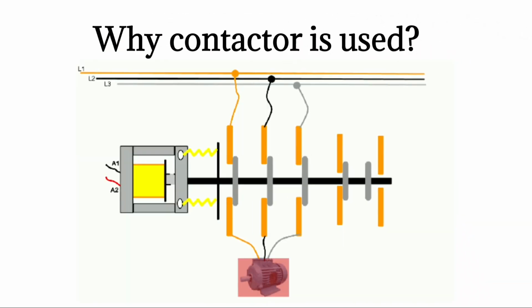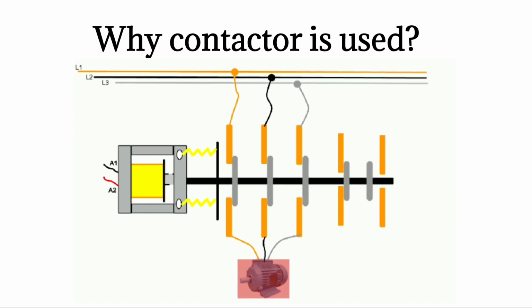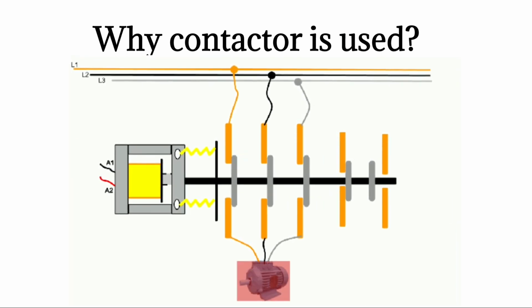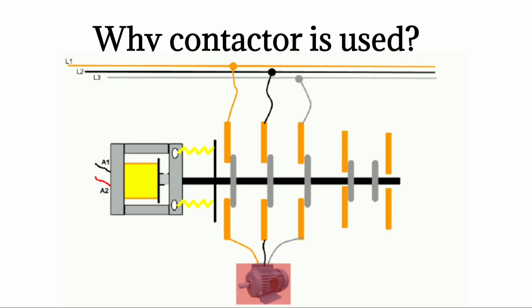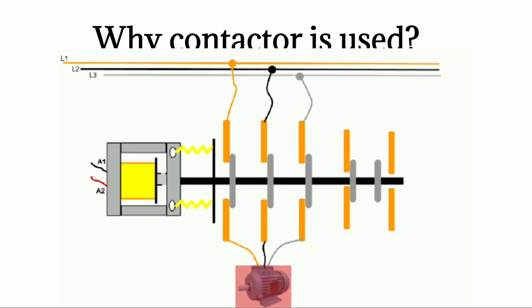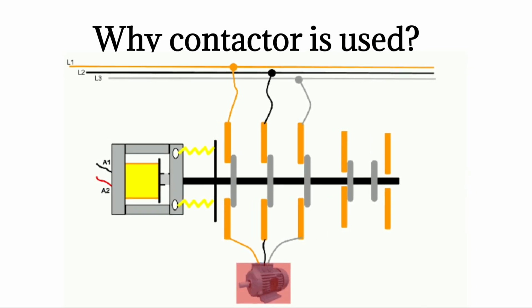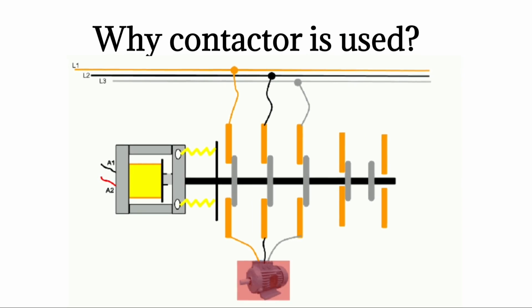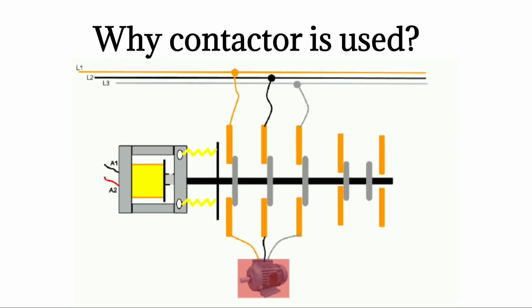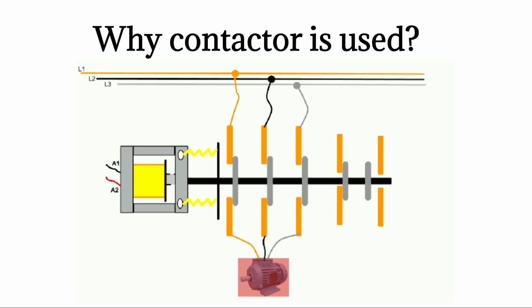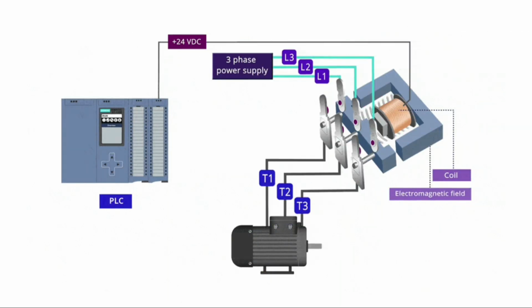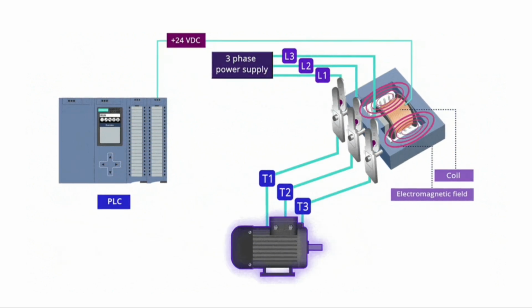Now you may ask, why do we need to use a contactor? Can't we connect the motor directly to the PLC? Well, the short answer is no. Why? Because you don't want to connect a high voltage electric motor to your shiny expensive PLC directly. This will damage the PLC cards if there are any electric surges on the motor's side. So, what we do instead, we use a contactor to connect the PLC to the motor indirectly and safely.